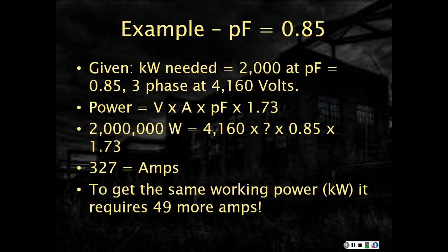Let's say our power factor is 0.85. Again, I still need that same 2,000 kilowatts. The power factor has dropped to 0.85. I still have a 3-phase electrical distribution system at 4,160 volts. Again, I'm going to solve for amp draw. And this time, with the new power factor, my amp draw has gone to 327. I'm still needing the same working power. That hasn't changed. But it requires 49 more amps to accomplish that mission.